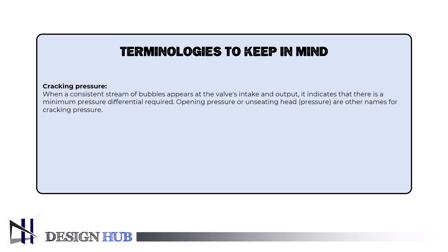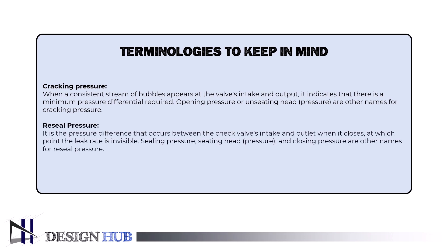There are some terminologies to keep in mind when going through a check valve. First is cracking pressure: when a consistent stream of bubbles appears at the valve's intake and output, it indicates a minimum pressure differential required. Opening pressure or unseating head pressure are other names for cracking pressure. The second is reseal pressure: the pressure difference between the check valve's intake and outlet when it closes, at which point the leak rate is invisible. Sealing pressure, seating head pressure, and closing pressure are other names for reseal pressure.